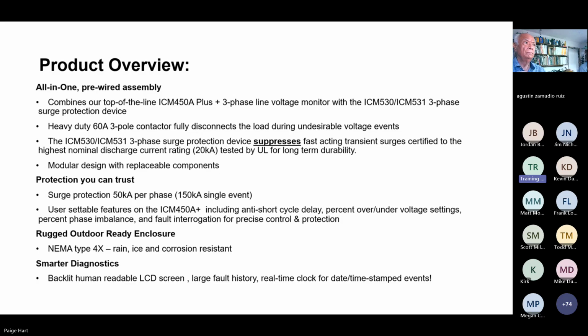And they're like, what's going on? Well, they put a 450A plus in there and he found out that, at 2 o'clock in the morning, some other gigantic piece of equipment was turning on, dropping the voltage below the allowable voltage for his equipment, and it was triggering a safety shutdown. So he could then fine tune his operation so that that wouldn't happen at that time and he wouldn't have to be called out on a service call. So these are great diagnostics to have, great tools to have.